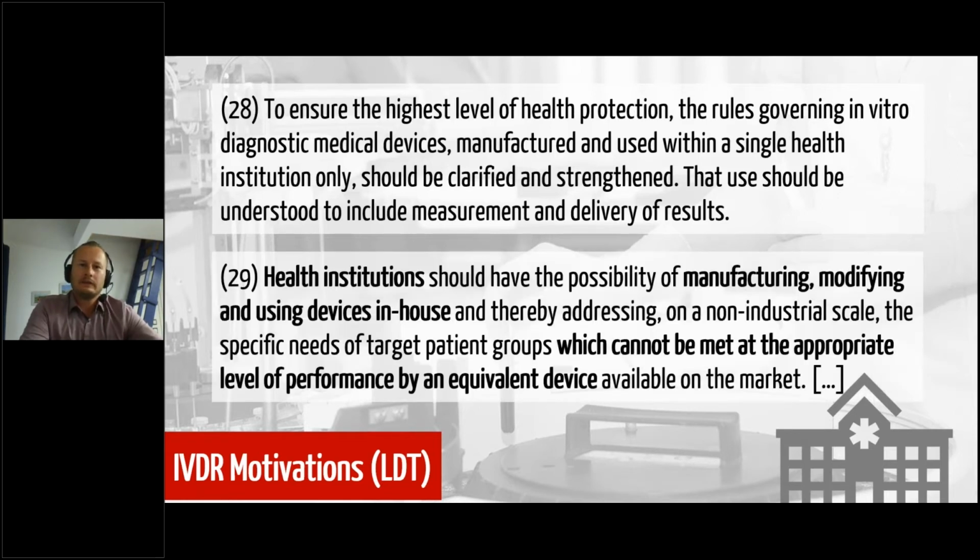And the second motivation was that health institutions should still have the possibility of manufacturing, modifying, and using devices in-house, and thereby addressing, on a non-industrial scale, the specific needs of target patient groups, which cannot be met at the appropriate level of performance by an equivalent device available on the market. So this is heavily impacting the medical laboratories, since they need to prove that there is no device on the market with an equivalent performance.